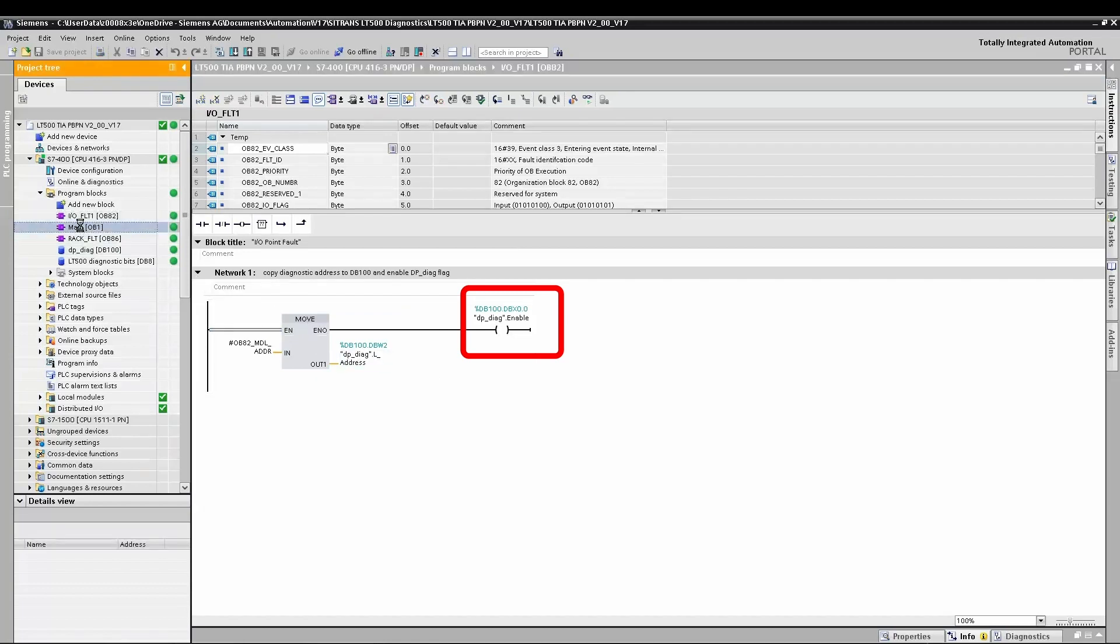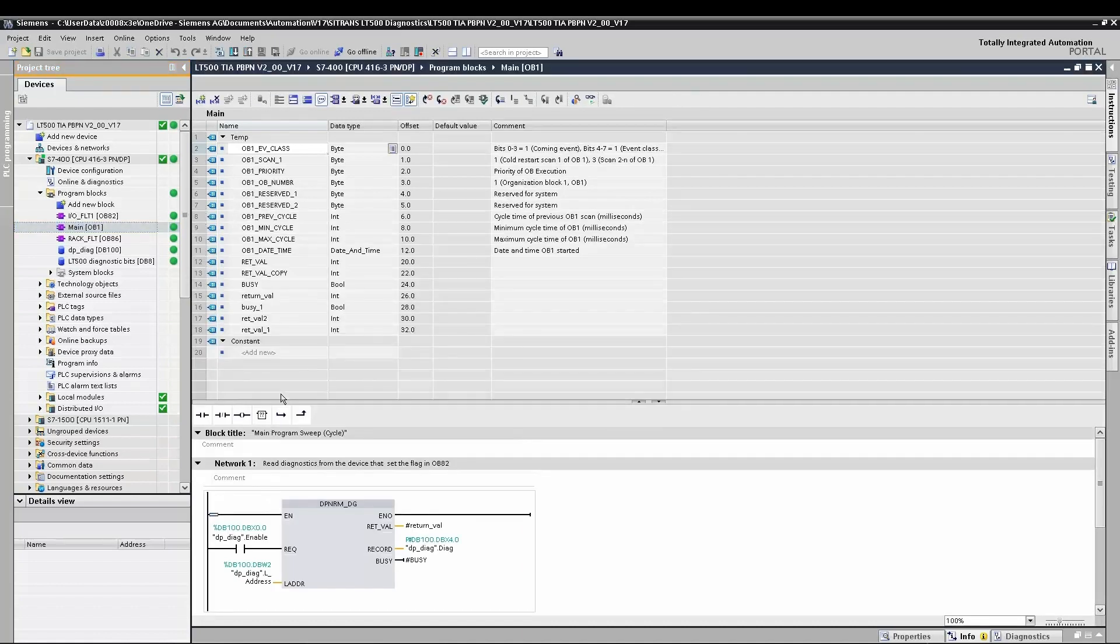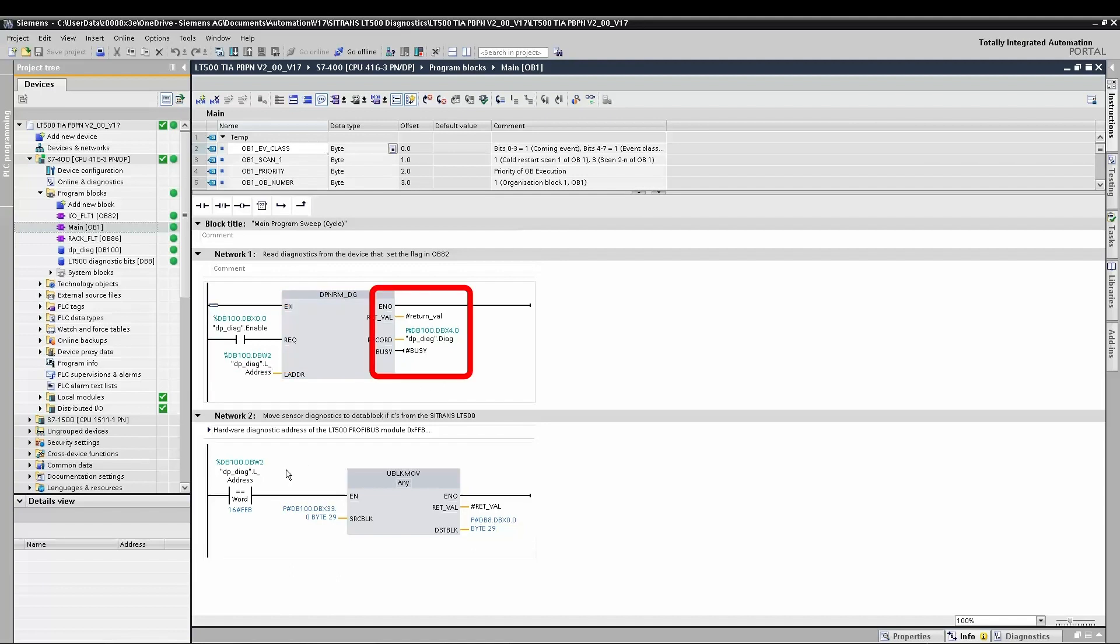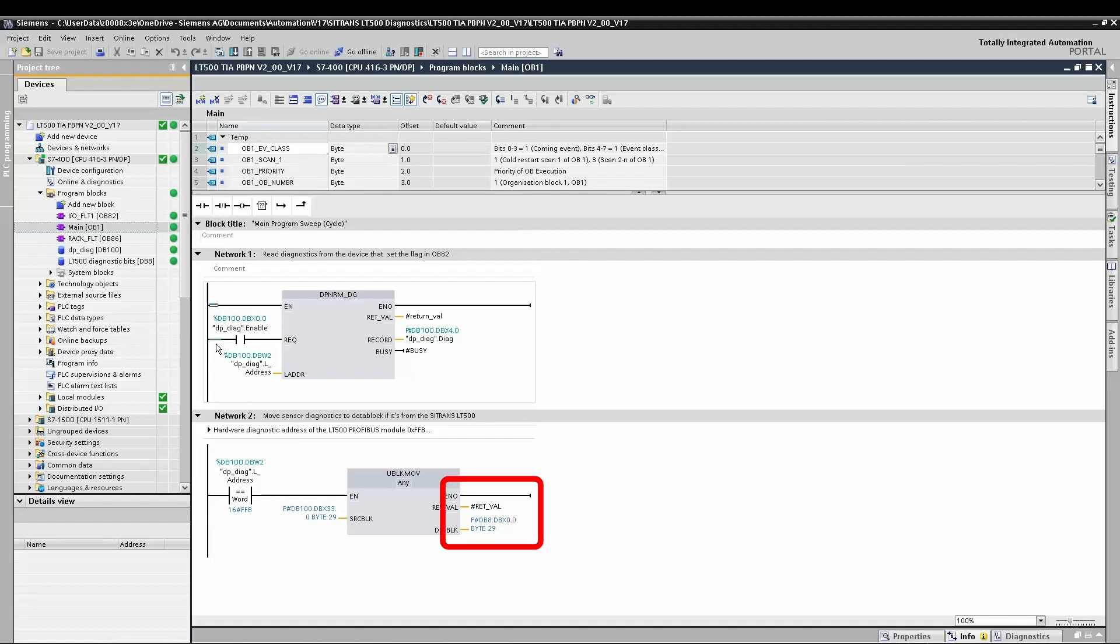We're going to monitor the dp-diag bit in our main program. We monitor the dp-diag bit, and when it's set, we copy the data from the diagnostic buffer into data block 100. If that diagnostic is from the Sitrans LT500 by looking at the module address, we then copy that sensor and transmitter information across to data block 8. This is purely for ease of reading in this example.